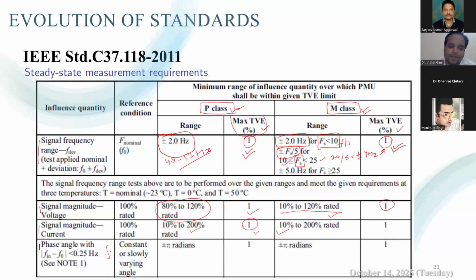So if your fundamental frequency F0 is, let's say, 50 hertz, and your actual frequency Fin is also 50 hertz, and at some moment the frequency of the signal changes to 49.8 hertz, the difference between the fundamental frequency and actual frequency is 0.2 hertz. The limit is 0.25 hertz, so it may vary up to 49.75 hertz. Even if the main signal is not 50 hertz, your PMU must measure the phasor with a maximum total vector error of 1%.